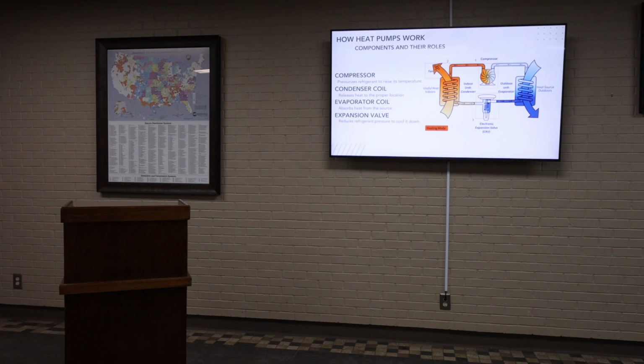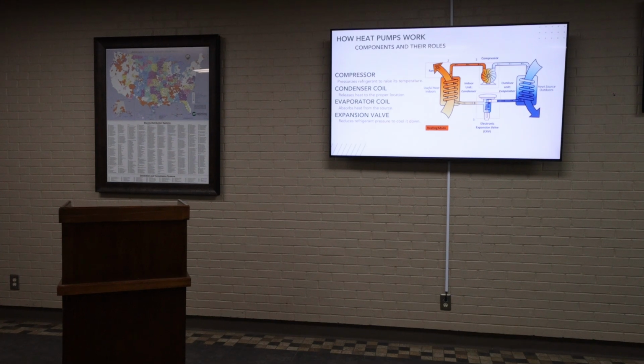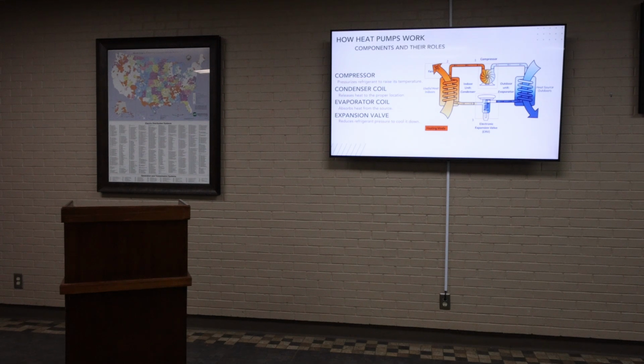So with an air source system, when it's 60 degrees outside, it can be a 4.0. But geothermal thinks it's that all the time, which is where we really pull ahead. Based on weather bin data over the last 100 years in this part of the country, we're at 30 to 40 degrees in the winter more than any other temperature—more hours at that range than anything else. When you compare that to a conventional heat pump, that's its threshold, around that 30-degree mark, when you set up dual fuel systems. Some customers I can get by setting them to switch over at 35, some want it at 40, depending on how they feel the heat is. But once you dive below that, efficiency drops off very quickly.